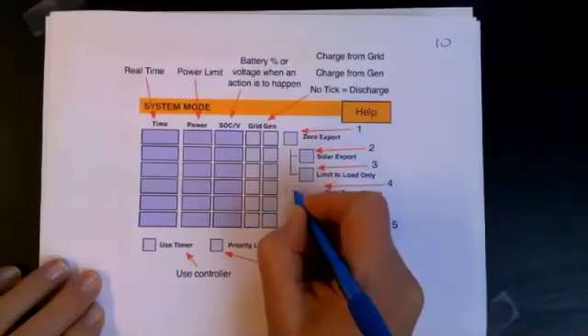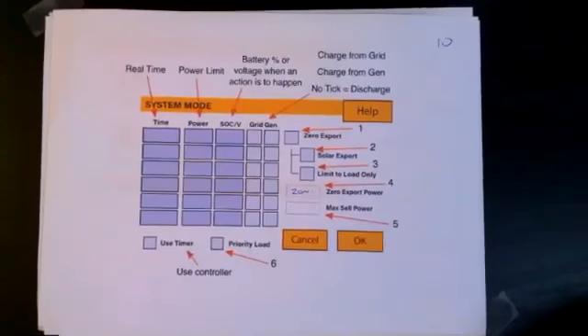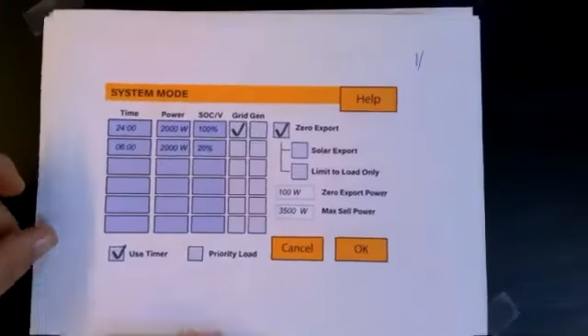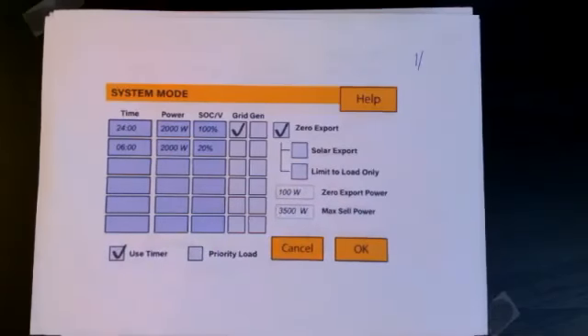So what we have to do is allow a small amount of power, because when you've got a single wire, there will be a voltage level on the wire, and the prepaid meter may see a power, and because of the speed or whatever, there's a very slight chance of a small amount of current passing in reverse. So to prevent that, we allow the power to pass one way. So typically on the zero export setting, we might put 20 watts. Some meters are very sensitive, so we might put 100 watts here, but you want to keep that as low as possible. 100 watts is a bit high, maybe 50 watts, depending on the meter.